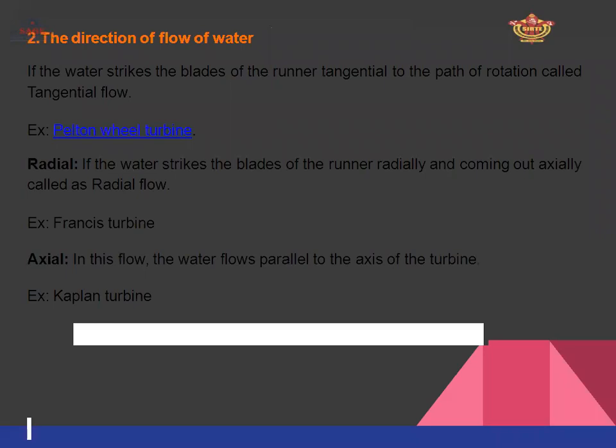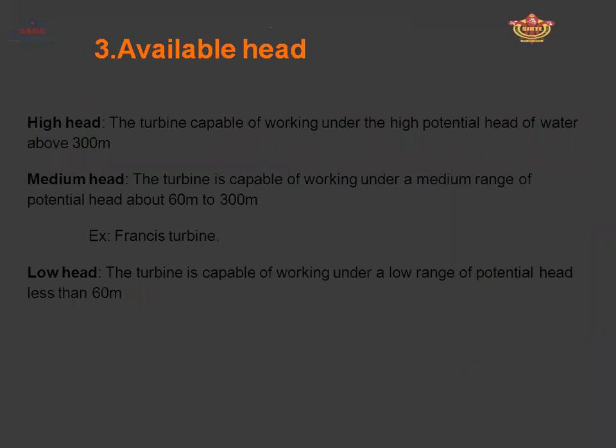When water flows parallel to the axis of the turbine, it is called an axial flow turbine. The Kaplan turbine is an example of an axial flow turbine. Regarding head classification: there are high head, medium head, and low head turbines. A high head turbine works above 300 meters. A medium head turbine works from 60 meters to 300 meters, and the Francis turbine is an example of a medium head turbine.